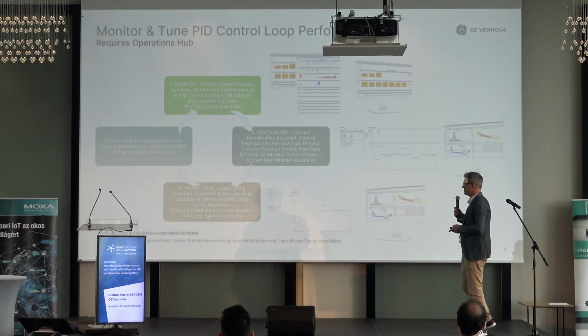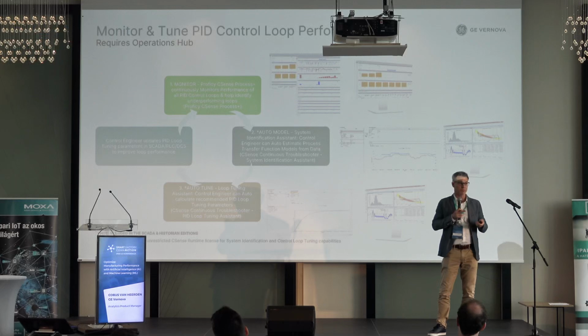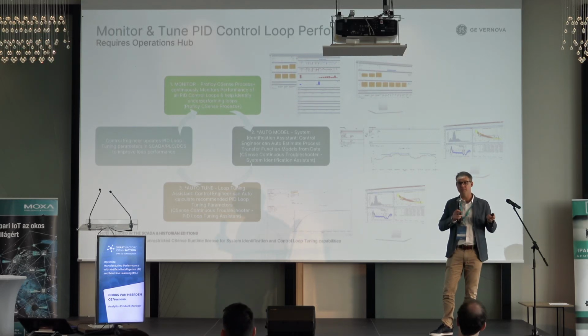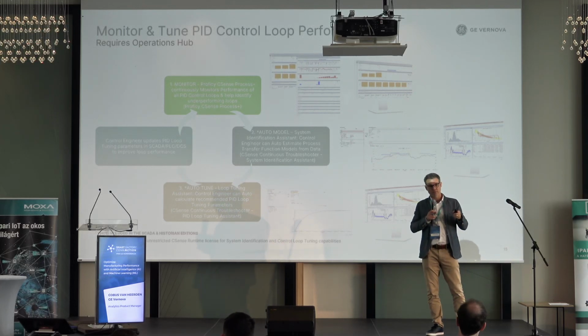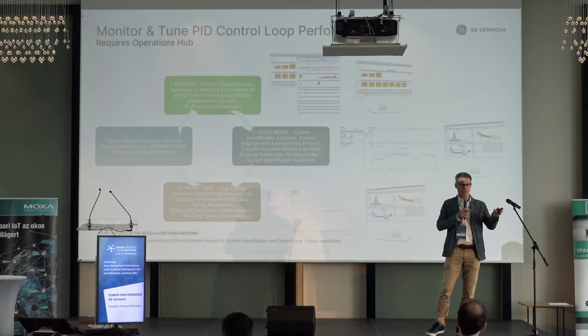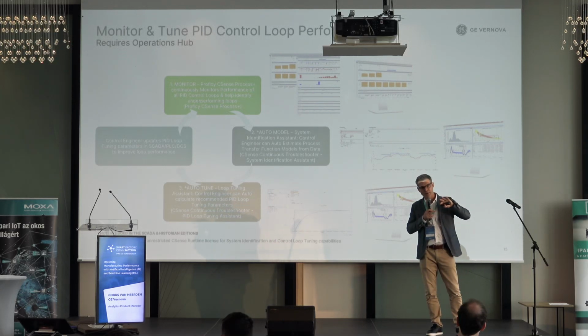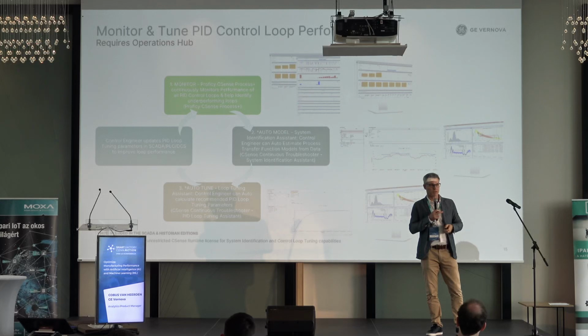PID control loops. SCADAs are often connected to PLCs, which normally have many PID control loops that control your equipment. If these loops are not working well, and they typically degrade in performance over time, why? Because the process changes or the machine ages. You need to retune them. Maybe the sensor is not working well, or the actuator, the pump, the valve, whatever it is controlling is not working well. Maybe the loop needs new or better PID settings. If these loops are not working, they create a lot of variation. That variation will break your equipment over time and will result in bad quality production over time.